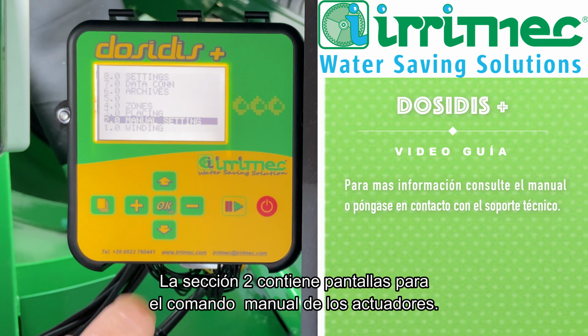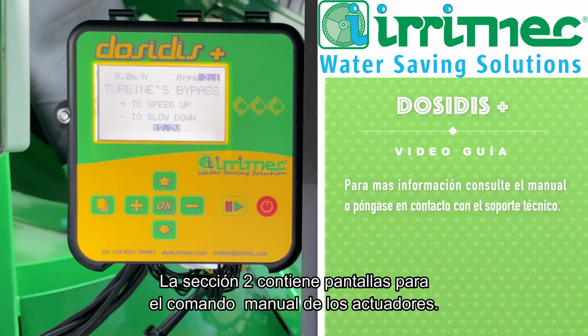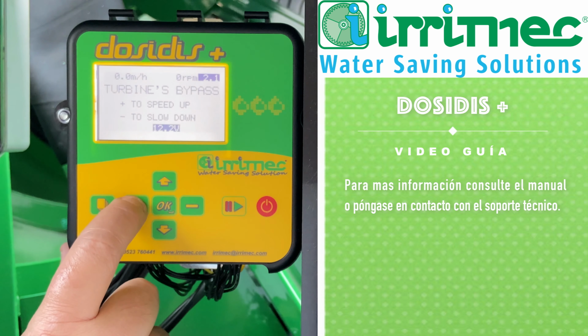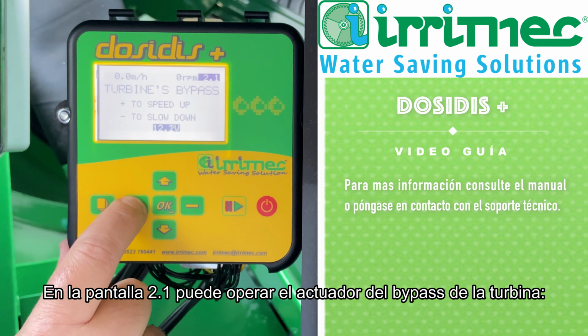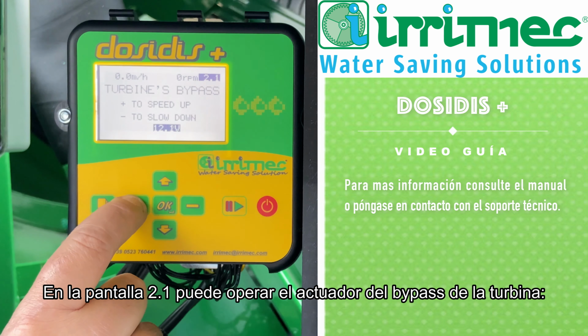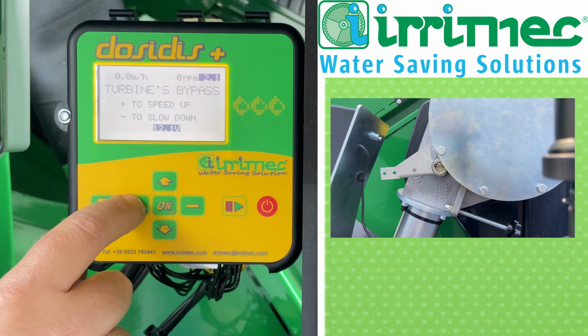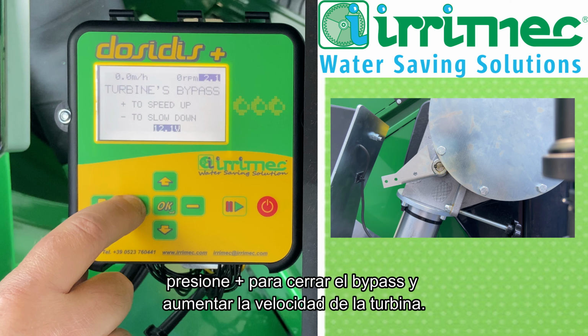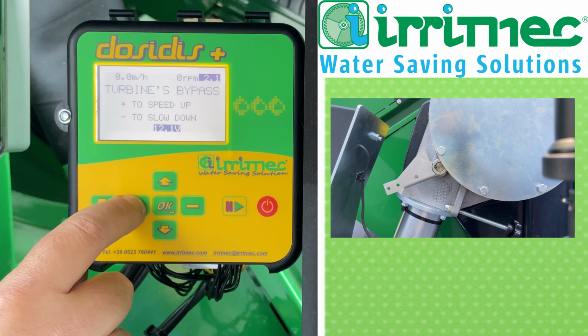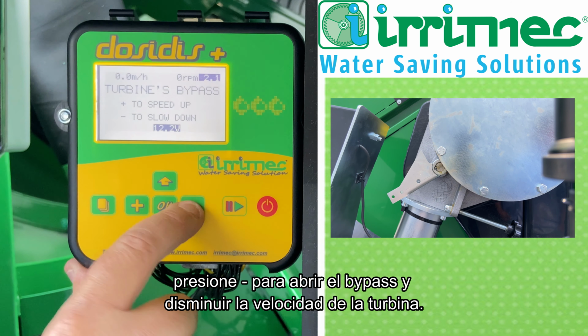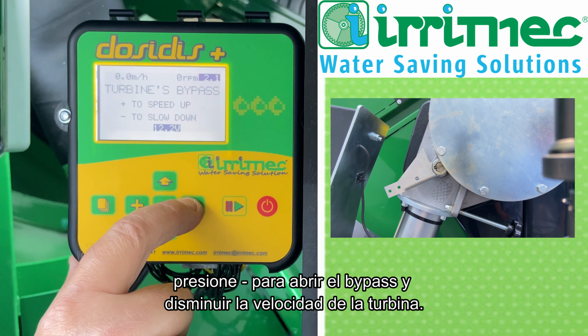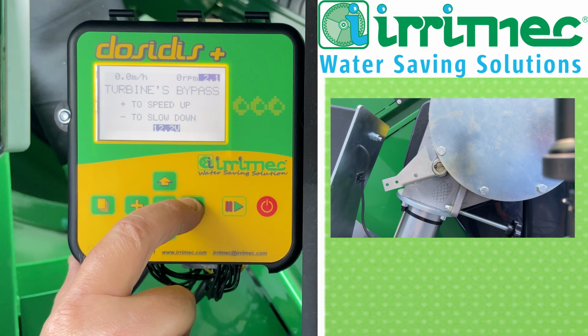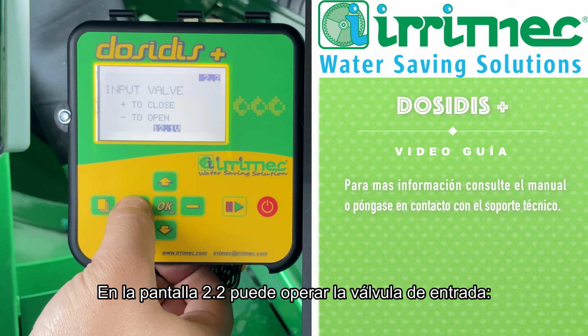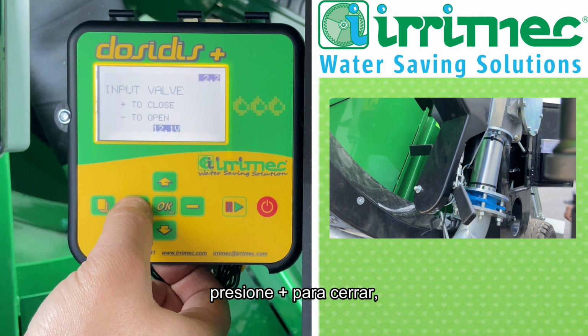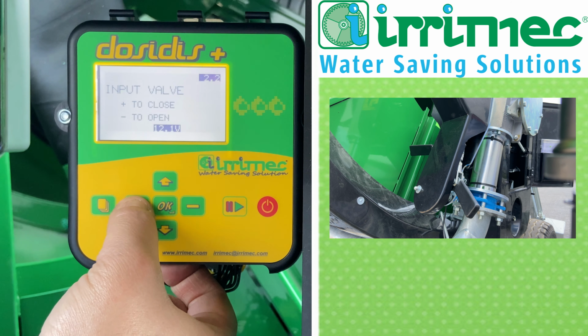Section 2 contains screens for manual movements of the actuators. On screen 2.1, you can operate the turbine's bypass actuator. Press plus to close the bypass and increase turbine speed. Press minus to open the bypass and decrease turbine speed. On screen 2.2, you can operate the input valve. Press plus to close. Press minus to open.